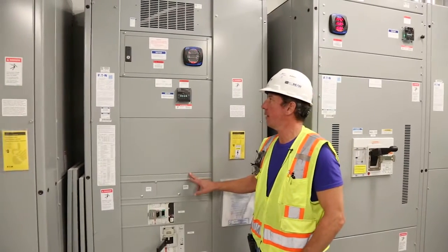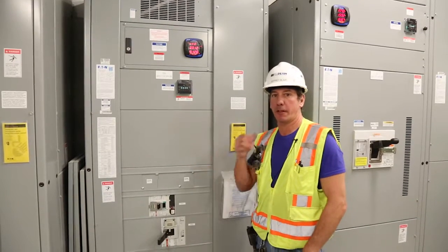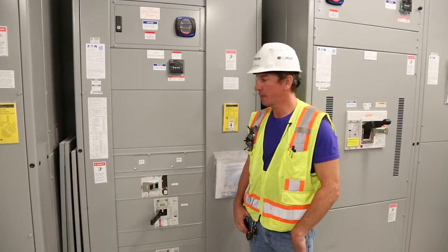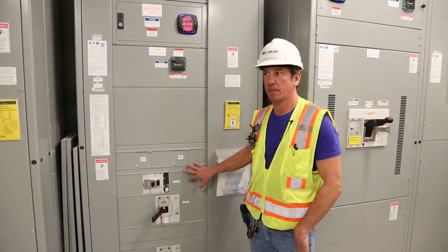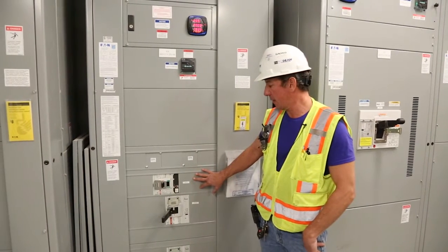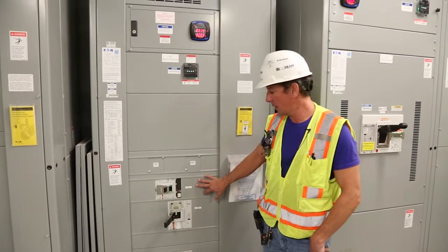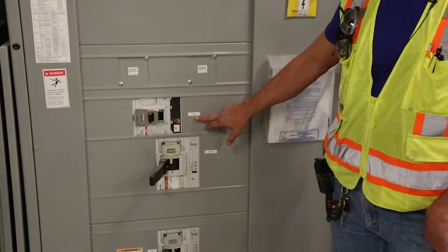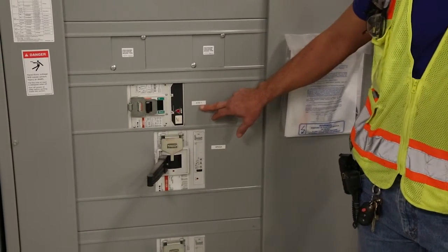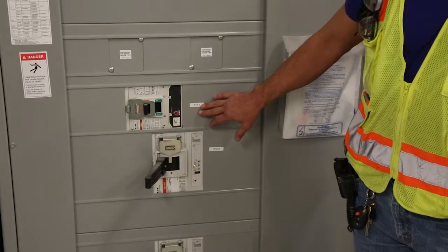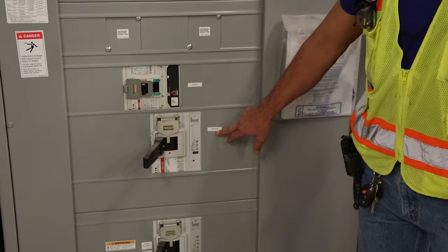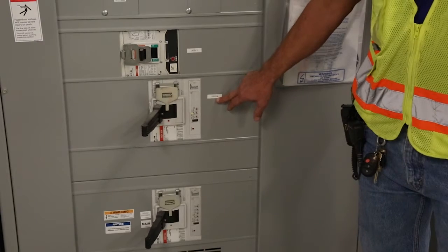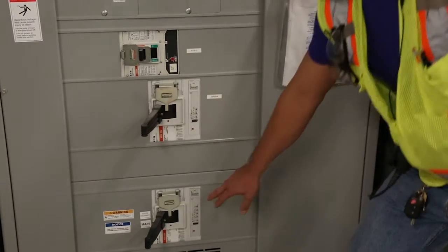All right, this is VOA. VOA's primary function is 277/480 volt power in the south tower. This primarily does all your lighting, mechanical, anything like that in the south tower that requires a higher voltage. Also in this panel, you have ATS1. ATS1 is going to feed all your emergency lighting, receptacles, anything of that matter in the south tower. Then you have DPVOA. DPVOA is all your 277/480 volt panels in the south tower, which that's going to feed. And then you have your main breaker here.